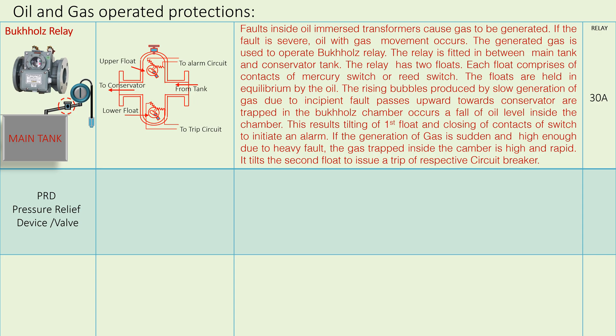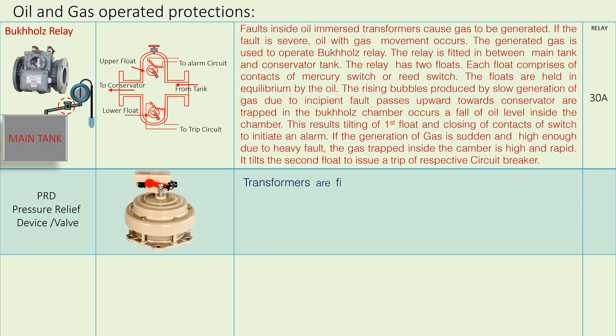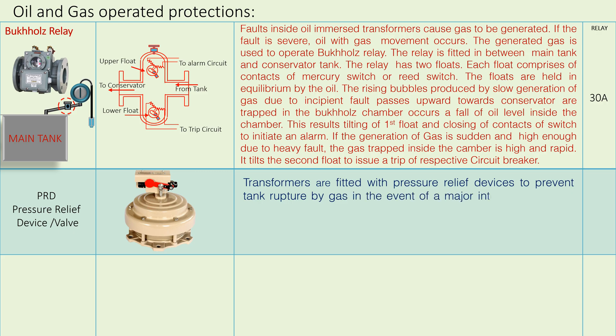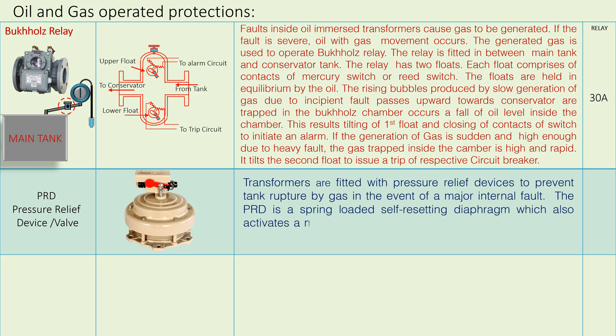Pressure Relief Device (PRD) or valve: Transformers are fitted with a pressure relief device to prevent tank rupture by gas in the event of a major internal fault. The PRD is a spring-loaded, self-resetting diaphragm which also activates a micro switch to issue a trip of the circuit breaker of the transformer.